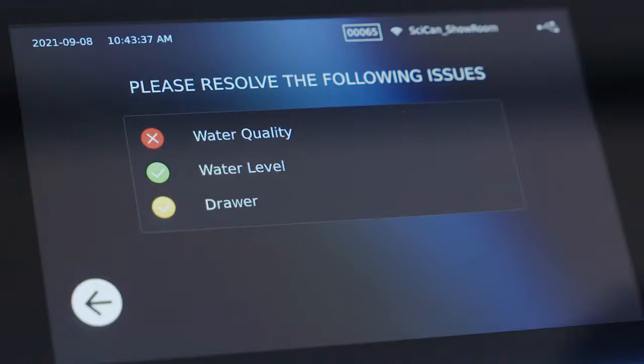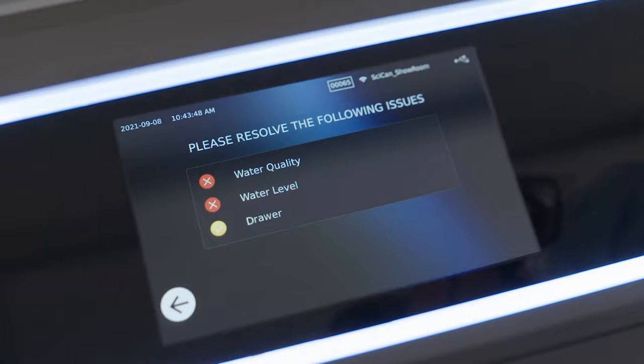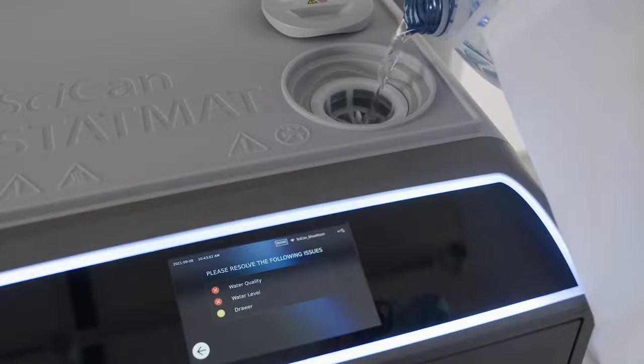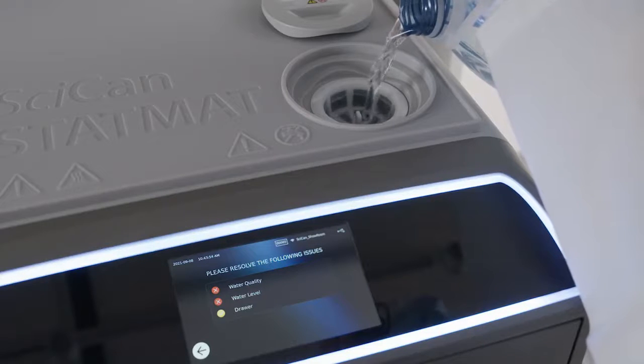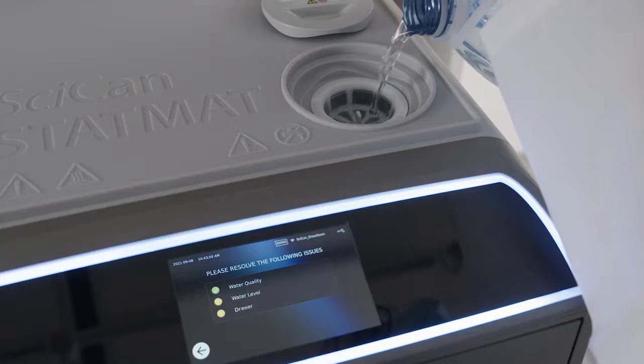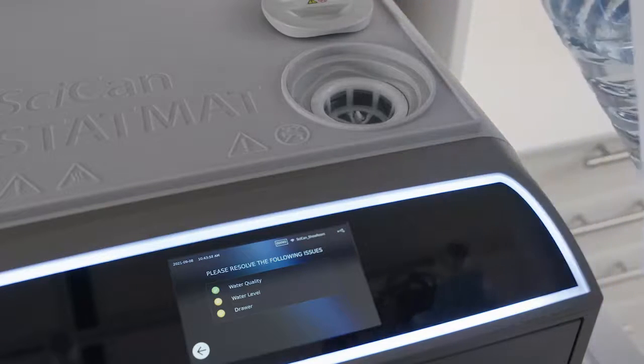If there's a red X next to water quality, drain the reservoir and refill with deionized, demineralized, or steam-distilled water. A red X next to water level and water quality means the water level is too low to run a cycle. Add deionized, demineralized, or steam-distilled water to the water reservoir to correct this condition.